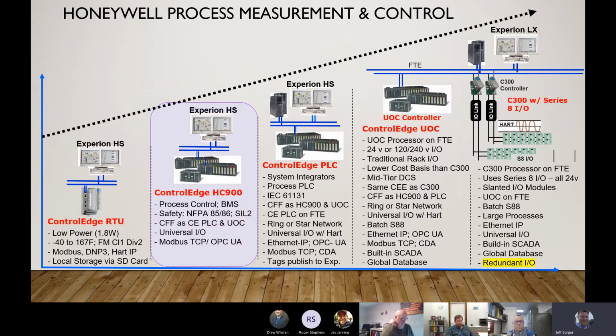We recently did a project where we have some safety LEL gas detectors which are communicating Modbus into the HC900, and it really allows a nice bi-directional communication path to share information without having to utilize the I/O cards on the HC900. The perfect application for the HC900 is if you have a system that has 4 PID loops or more, along with trending requirements, recording requirements, or in addition I/O, which you're using for discrete control. The HC900, that's really a perfect fit for that product.